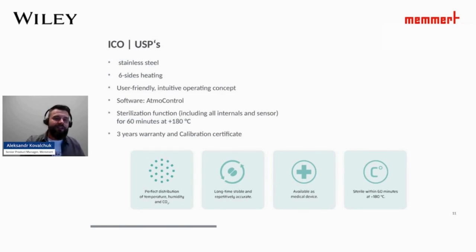Additionally, every incubator includes a comprehensive sterilization function that sterilizes all internal components and sensors at 180 degrees Celsius for 60 minutes, ensuring a contamination-free workspace. On top of that, the incubators come with a 3-year warranty and a calibration certificate, giving users peace of mind with reliable performance and verified accuracy.